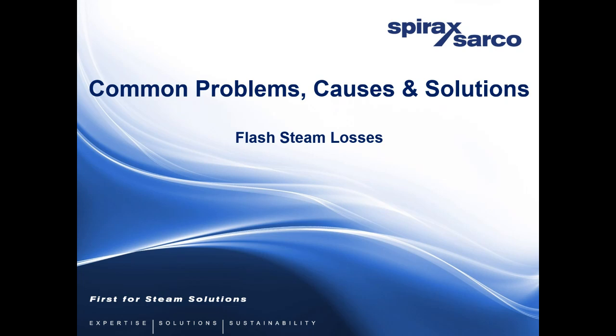Also, there is another question. What is a recommended frequency to change steam traps, safety valves, etc. in a steam line? When we talk about inspection and service, we talk about them as two different items. So your steam system should be inspected, depending on your use, every 6 to 12 months. Now, that doesn't mean replacement. That just means you want to know what's happening in your steam system. For a trap, on a healthy system, so please bear that in mind, maintenance on a steam trap should be every 2 to 3 years. However, if you're seeing more corrosion and erosion, those times will shorten, and they can shorten dramatically. There are other factors such as insulation as well, and proper control.